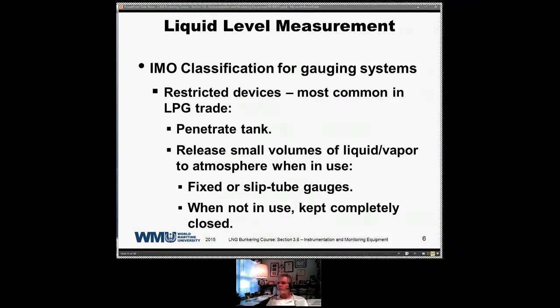Then we have what are called restricted devices. These are the most common in the LPG trade. They penetrate the tank and they release small volumes of liquid or vapor to the atmosphere when in use. I, unfortunately, have never had the opportunity to work in the LPG trade, so I have no experience whatsoever with this type of gauging system. The types of systems they refer to here are fixed or slip tube gauges, and when not in use, they're kept completely closed.